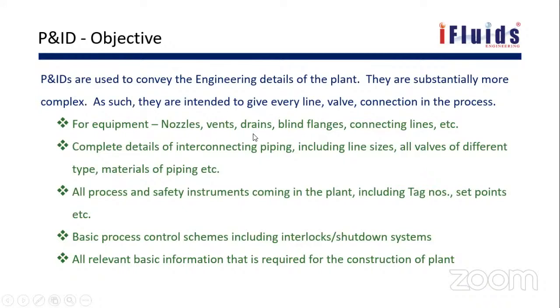Drain is to drain the complete liquid before going for maintenance. And blind flanges, before going for maintenance, you will be blinding all the inlets and outlets so that when a person is going for work inside the equipment or vessel, no fluid will come inside, so that you will be doing a positive isolation.